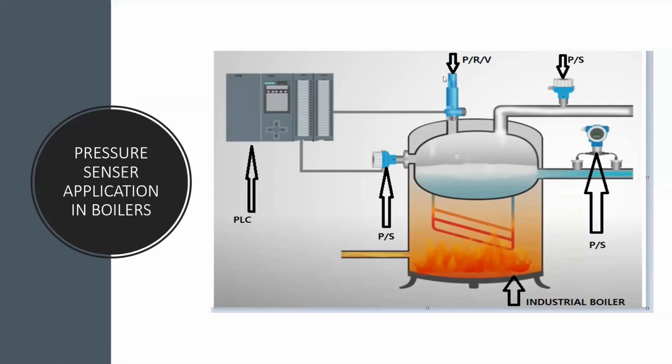For example, you can see here we have PS1, where we are monitoring the boiler directly just to observe and view the pressure that is in the boiler itself. We also use a pressure sensor in this case to indicate the pressure. For example, if the pressure of the boiler is 12 bar, just for example, and then we are firing the boiler more without consuming what we fire.